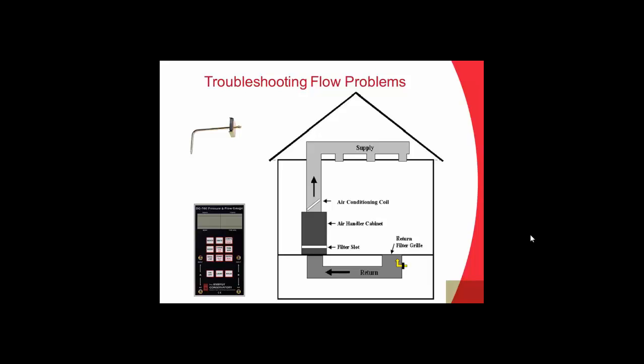We want to be measuring static pressure, so we use our static pressure probe, and we're going to connect that up to channel A and turn on our DG700, and we're seeing a measurement of -8 pascals. I'm not sure how well you can read that, so I put the -8 here because maybe it's not showing up well enough on the gauge, but we're measuring -8 pascals.